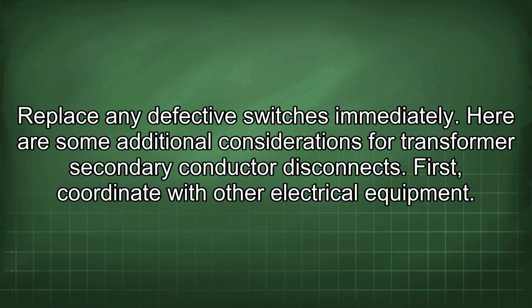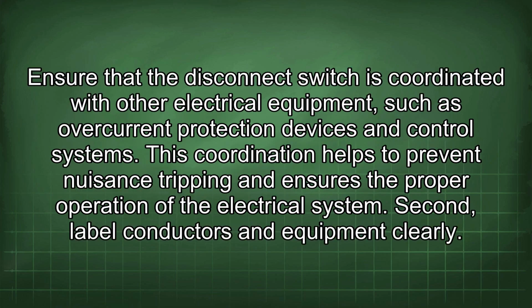Here are some additional considerations for transformer secondary conductor disconnects. First, coordinate with other electrical equipment. Ensure that the disconnect switch is coordinated with other electrical equipment, such as overcurrent protection devices and control systems. This coordination helps to prevent nuisance tripping and ensures the proper operation of the electrical system.